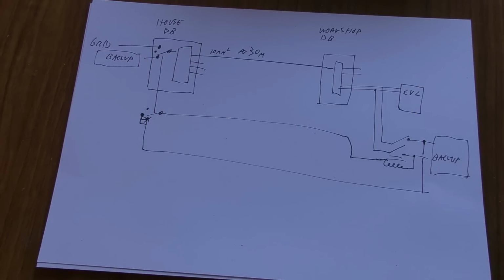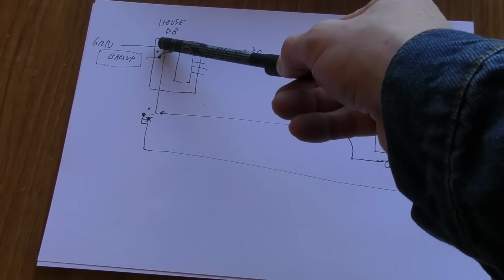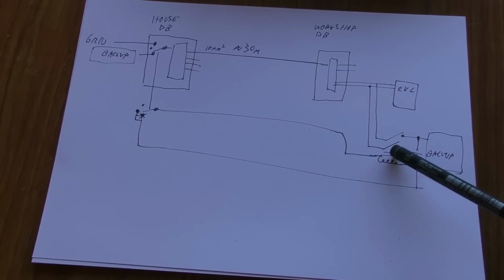So what would be nice is if there was a way of getting a version of that center off switch which had an additional auxiliary connection that only closed when it's in that center off position, which I've not seen anything vaguely resembling that. You'd have to cobble something together mechanically, but that then provides a safety interlock, so that if this was ever removed from the center off position when the backup was active, it would drop the contactor out and disconnect the backup source.